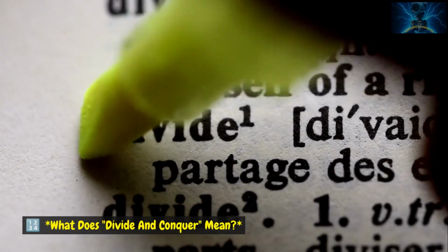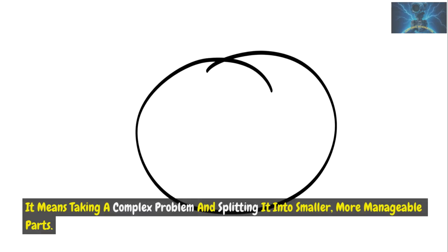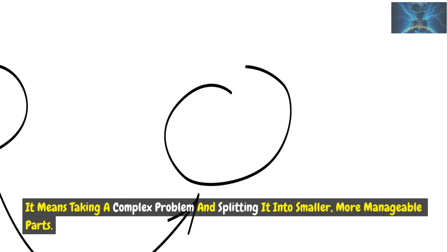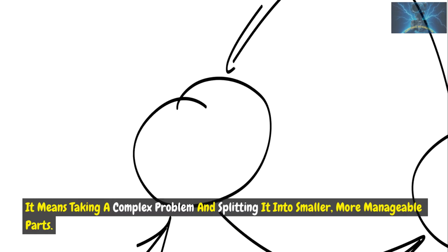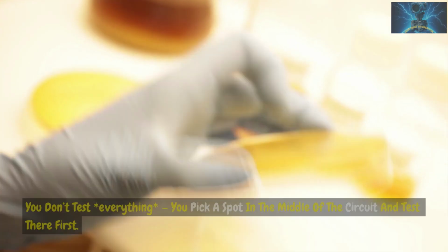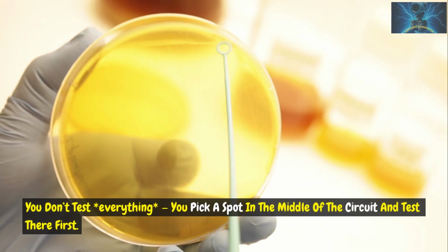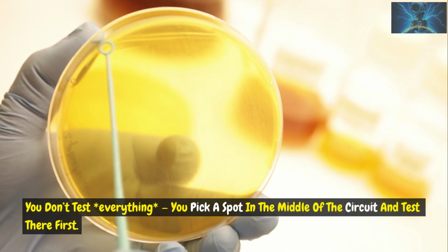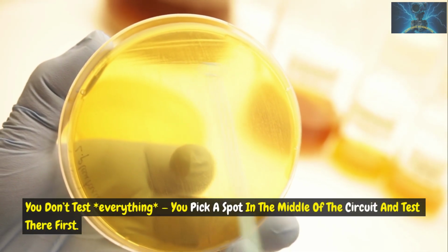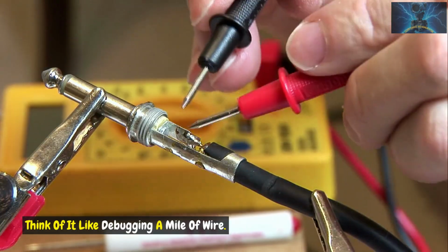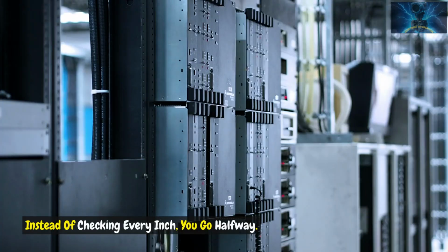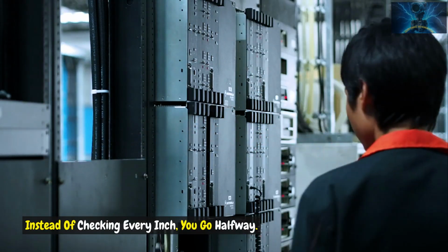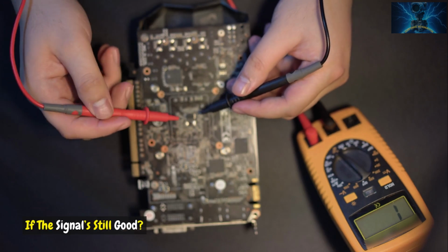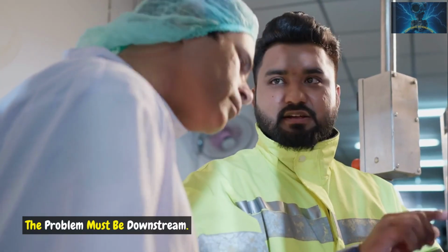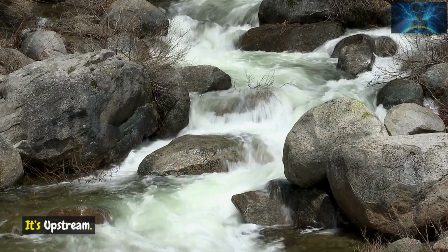What does divide and conquer mean? It means taking a complex problem and splitting it into smaller, more manageable parts. You don't test everything. You pick a spot in the middle of the circuit and test there first. Think of it like debugging a mile of wire. Instead of checking every inch, you go halfway. If the signal's still good, the problem must be downstream. If it's not, it's upstream.